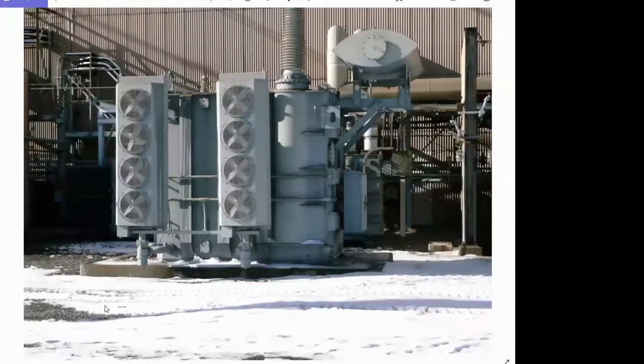This gives an idea of the size of the transformers. What they're protecting are the step-up transformers just outside the power plant. On the other side of this wall is the generator, the most expensive piece of equipment in the plant. They protect the under-turbine lube oil using 3% F500, so if these catch fire, they can extinguish them before it spreads into the power plant.